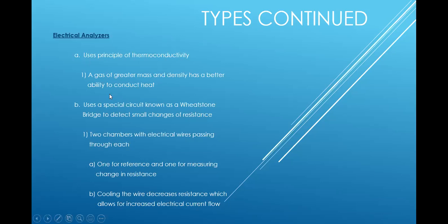But anyway, I digress. The electrical analyzer uses the principle of thermoconductivity. A gas of greater mass and density has a better ability to conduct heat.